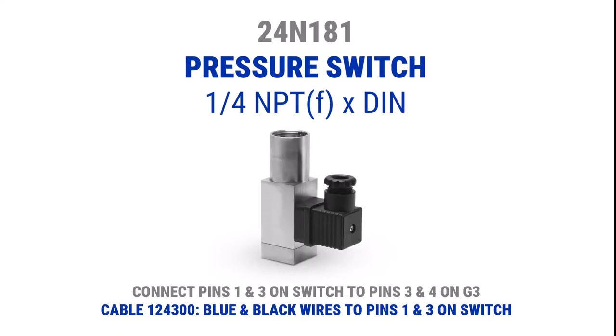24N181 is a Barksdale 9000 series switch often used on mobile equipment. It uses a DIN connector for its wiring. It's also a dry contact switch, so only 2 wires need to be used to connect it. Again, the polarity doesn't matter, so as long as pin 1 common is connected to either 3 or 4 on the M12 and pin 3 normally open is connected to the other one, the switch should work. If you choose to use our M12 cable part number 124300, then the blue and black wires are the ones that connect to pins 1 and 3 on the switch's DIN connector. The white wire and the brown wire are not used, so they can be clipped off of the 124300.